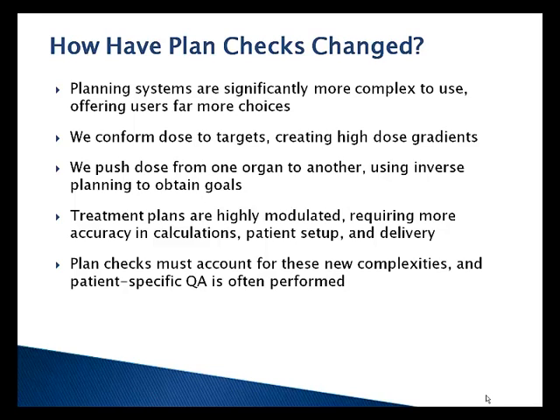And we accomplish all this with modulation. The MLC leaves moving over and over and over again. One of the main points of this talk is going to be the more modulated your plan is, the more you've magnified all of your calculation errors and all of your patient setup errors and all of your delivery errors. So it's not something that's bad, that's how we get good conformal plans, but you have to keep in mind that you've magnified every error in your system for each additional MU you use to treat a patient each time you move your MLCs. So plan checks have to account for all these new complexities.